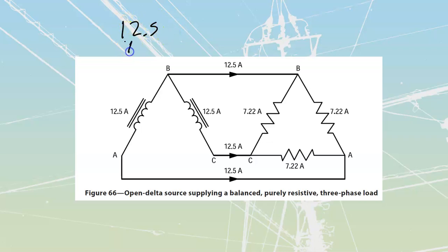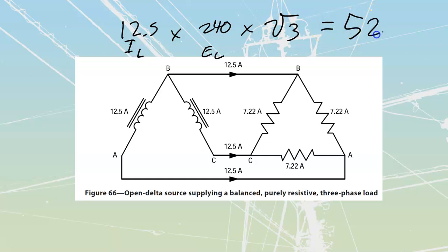12.5 I line. And if I multiply that by my E line, which is still going to stay the same, 240 over here, and then multiply that by root 3, I'm going to get the total kVA that I'm able to put out. So we multiply those together, 240 times 12.5 times root 3, which gets me to a value of 5,200 VA, or 5.2 kVA, whichever one you would prefer to use.